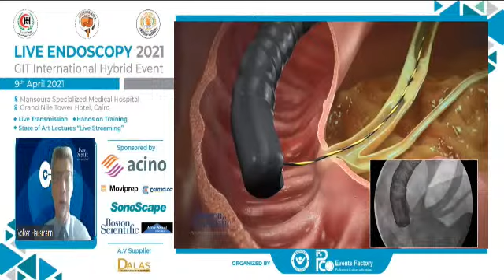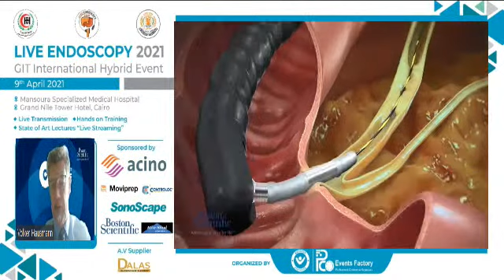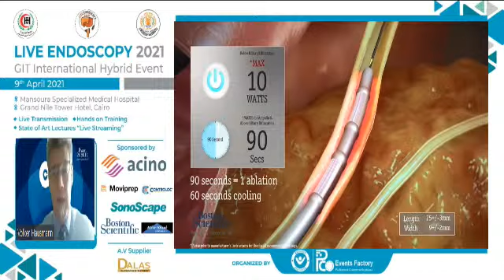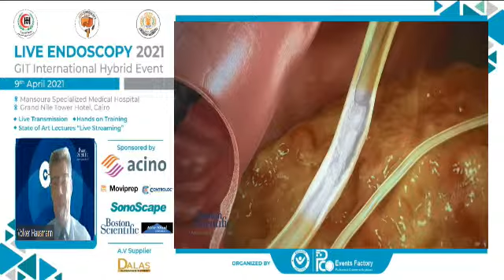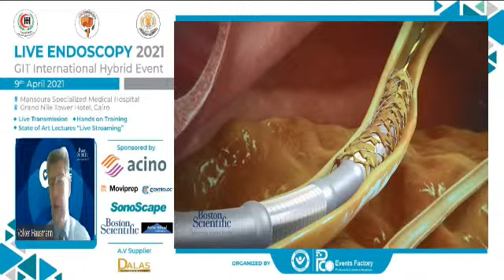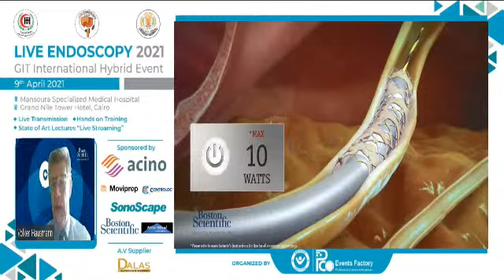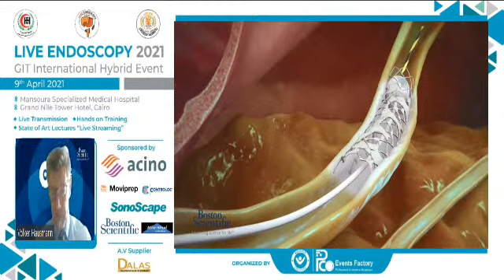Simple placement: you put your catheter over a guide wire into any kind of endobiliary stricture like that. You place the electrode in the middle of it. And what we're doing right now is basically slow cooking. We're simply heating it up with just 10 watts, not more, for 90 seconds and allowing it to cool down. This allows immediate application of an ablation of 25 millimeters in length and roughly 1 centimeter in diameter, meaning you immediately gain additional diameter. You can also use this catheter for cleaning an occluded metal stent. Similar procedure, 10 watts for 90 seconds, and then it's cooled down. It's really a very simple procedure. You do not have a big learning curve here. It's really easy to use.